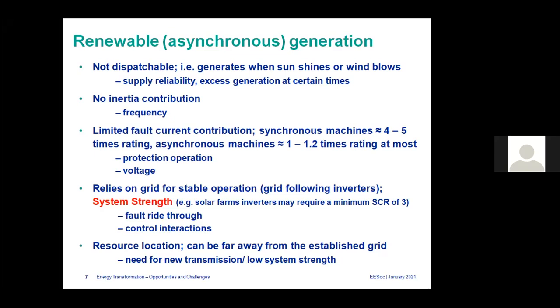Then the other issue is voltage control, especially voltage recovery during faults or just after faults. Synchronous machines help that much more than asynchronous machines. Then one other issue is the ability of the generators to ride through faults. Most of the present technology, grid following inverters in solar farms and wind farms, rely on the grid for their stable operation. They are called grid following inverters mostly, and we relate this to the term system strength. I have a couple of slides talking a bit more about system strength. For example, for solar farms to operate stably, you need a certain level of system capacity or system strength or fault level. It's called SCR. I will define that later on.